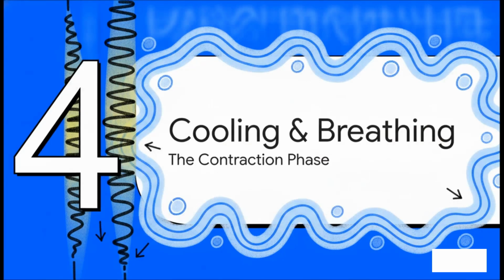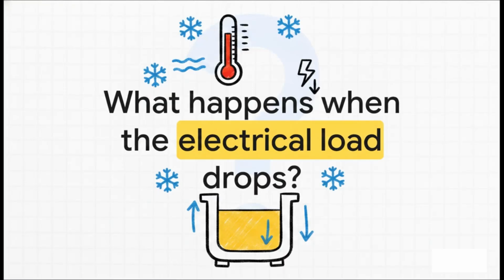Now for cooling down and breathing, the contraction phase. Because, hey, what goes up must come down, right? So what exactly happens when the peak demand of the day finally passes and the electrical load drops? Well, as the intense internal heat generation slows down and the physical temperature gracefully falls from that 95-degree peak all the way back down to around 30 degrees Celsius, the volume of the mineral oil naturally decreases. The physics we just talked about simply reverse themselves, and this massive body of oil begins to contract.